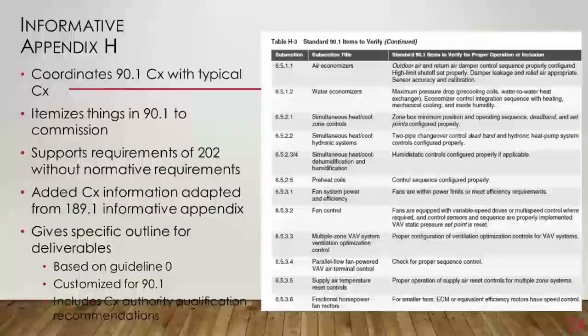Okay, also in the informative appendix, again, some of the language in the actual requirements is fairly general, for instance, HVAC just says commission all controls, or verify and test proper operation of all controls. It doesn't get into a blow by blow. However, in the informative appendix, we do have a 3-page table that lists everything in all of the discipline sections that we felt would be appropriate to provide some commissioning for. What section is it in? What's the topic of that requirement in the report? And then what type of things should be verified in there. Again, this is informative language. It's not mandatory, but it certainly would be a good tool for a commissioning provider to use in developing their scope in working with an owner. So that is again available in our informative appendix.